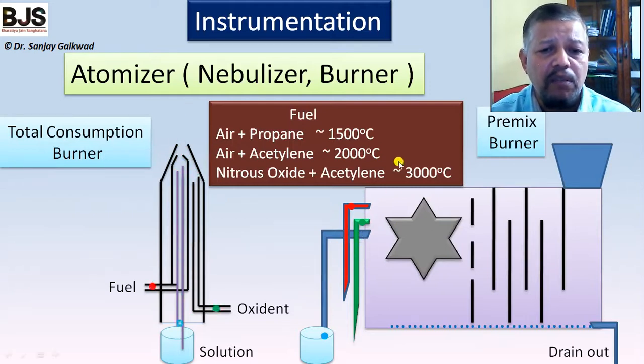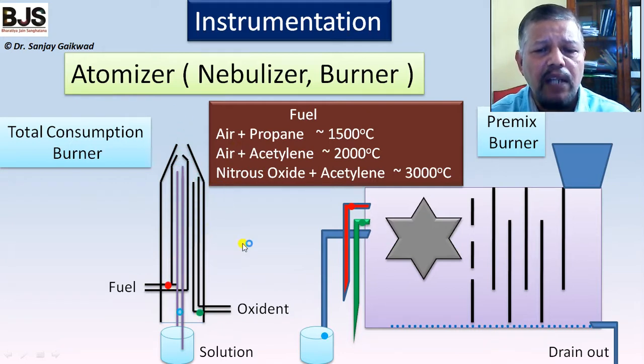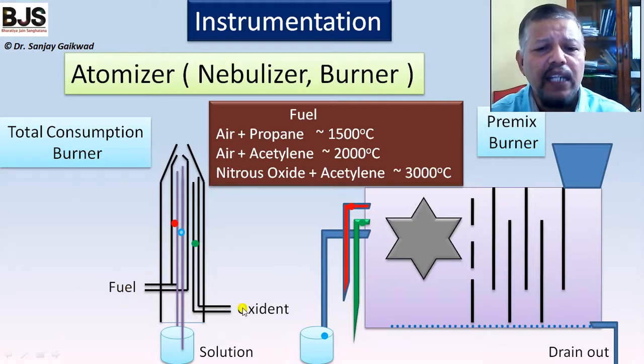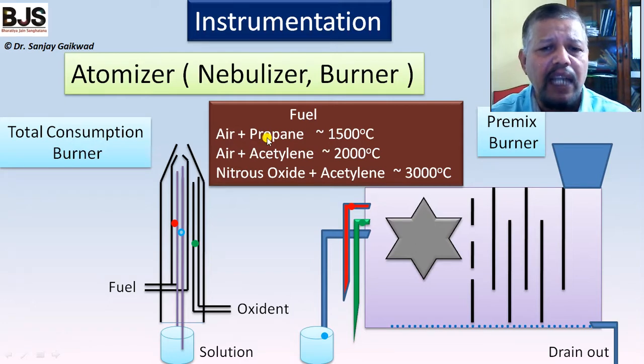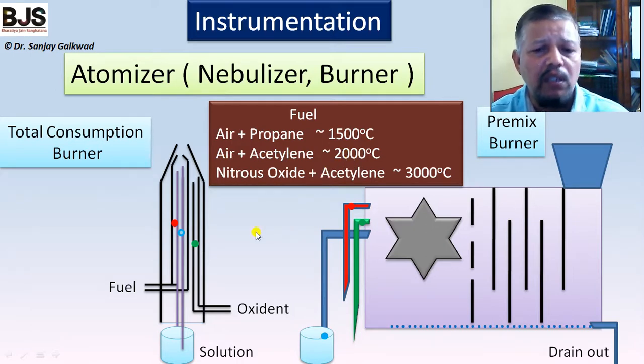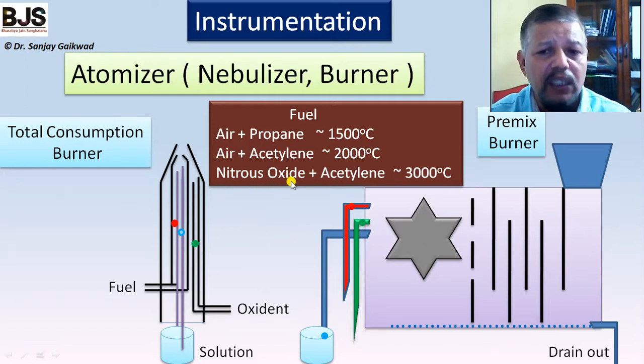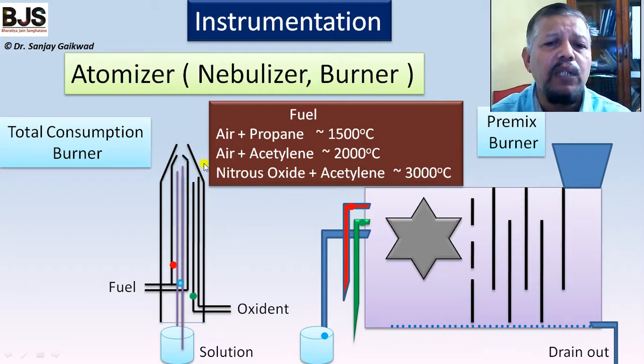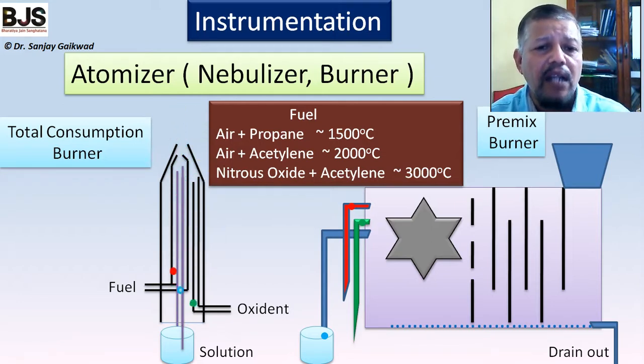Two types of burners are used: the total consumption burner and the premix burner. In the total consumption burner, the whole solution is transferred into the burner, and the fuel-oxidant ratio is maintained to achieve the required temperature. With air and LPG (propane), we reach up to 1500°C; with air and acetylene, 2000–2500°C; and with nitrous oxide as oxidant and acetylene as fuel, we can reach 3000°C, at which level metal ions transfer to atomic level and absorb radiation.